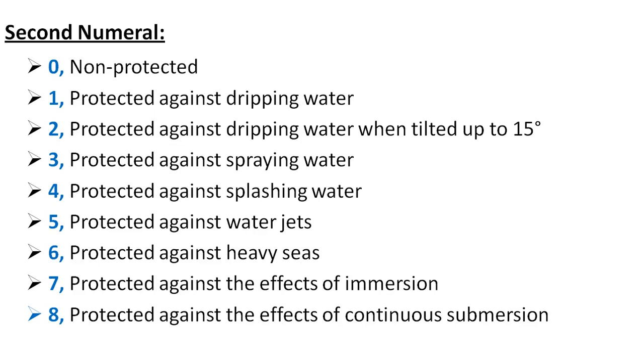Two indicates protection against dripping water in the vertical direction when the device or equipment is tilted at 15 degrees. Three indicates protection against spraying water, where water enters the device up to 60 degrees from vertical. Four represents protection against splashing water from all directions. When the second numeral is five, it is protected against water jets — limited ingress is permitted. Six indicates protection against heavy seas or powerful water splash jets, and water penetration should not have any effect on the operation of the equipment.